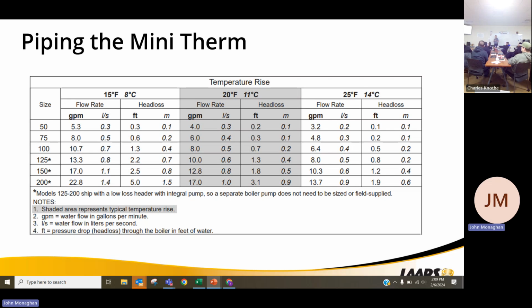So, piping the Mini Therms. Again, we go back to it. A lot of the issues with some of the products is they're not piped correctly, not pumped correctly, and they're not vented correctly. Now, when we're installing this product, we recommend usually a 007, is what comes on them. That 007E is capable of moving roughly around 16 gallons a minute or 160,000 BTUs.